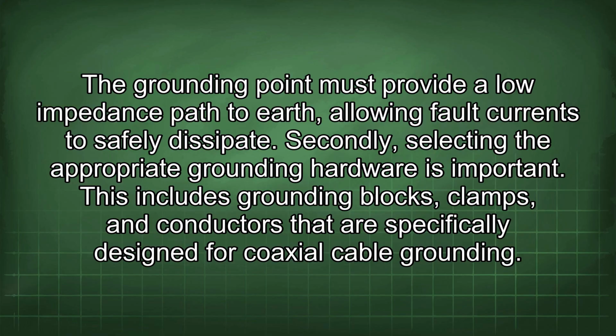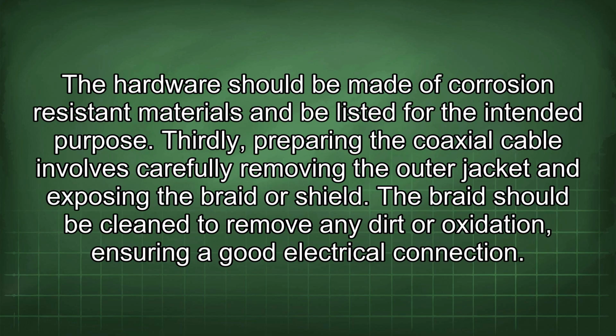Secondly, selecting the appropriate grounding hardware is important. This includes grounding blocks, clamps, and conductors that are specifically designed for coaxial cable grounding. The hardware should be made of corrosion-resistant materials and be listed for the intended purpose. Thirdly, preparing the coaxial cable involves carefully removing the outer jacket and exposing the braid or shield. The braid should be cleaned to remove any dirt or oxidation, ensuring a good electrical connection.